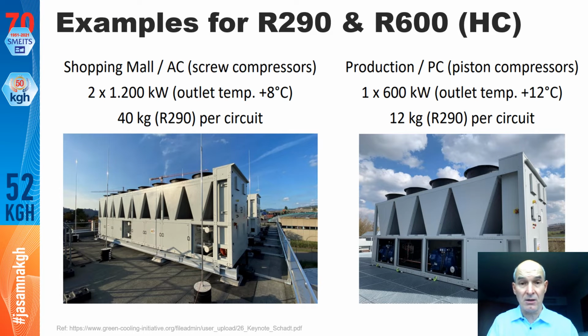So these are the large systems I would like to show you, just highlighting some examples from a German installation. These are shopping mall air conditioning compressors or units, condensing units, 2 times 1.2 megawatts with only 40 kilos of propane on the roof of this supermarket shopping mall.